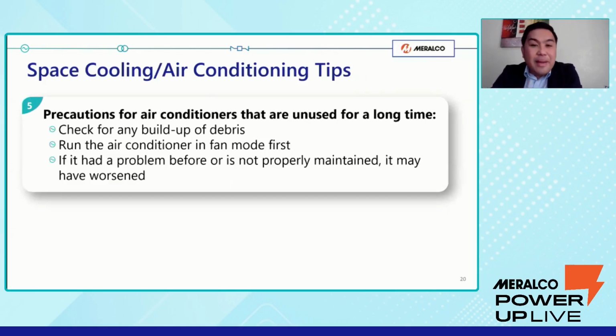Lastly, it would be best to be mindful of the ACUs that are left unused for a long time. So ano po yung mga pwede nating gawin? First is to inspect the unit and be sure that there is no build-up or debris, especially in the motor. Second, check the last maintenance date. Next, we should run the ACU in fan mode first to isolate the problems, if there are any. And we must remember that if our air conditioning unit had a problem before or is not properly maintained, it may be worse after a long period of sitting unused.